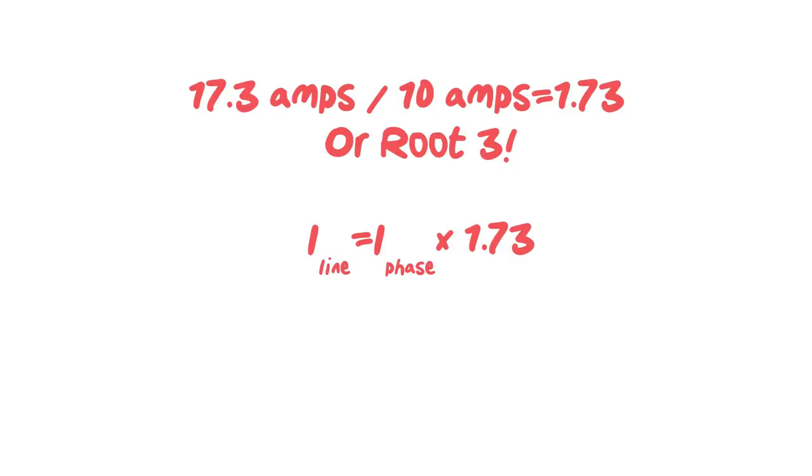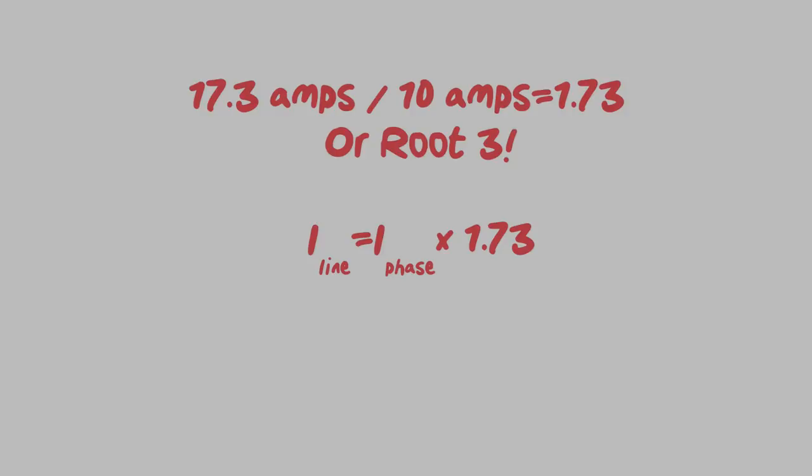So there you go. We have added all three of these up in every configuration to figure out what the A line was, the C line was and the B line was and it always worked out to be 17.3 amps. Which means if I take 17.3 amps divided by 10 amps, I get 1.73 or root 3. So for current in a delta configuration, I line is equal to I phase times 1.73. I could have used any different current. I could have used 246,333 amps per phase and then figured out what the line was based off of this here. So remember, if all that didn't make sense, at least if you can remember this, I line is equal to I phase times 1.73, you're going to be good.